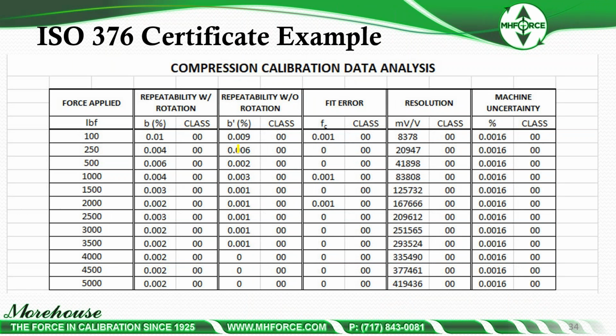So if you're issuing reports to customers or you're out in the field and you're using an ISO calibration, you will know your expanded uncertainty per ISO 376. And if we look at these in higher detail, you can see the actual numbers, 0.01, 0.004 per point. As I said, every one is tested per the load point, and this is why that 5% point is recommended. If this were to say class half instead of class 00, and the next point we did was at 500 pounds, the range assignment would be class 00 from 500. And that's why we like to do the 5% point.